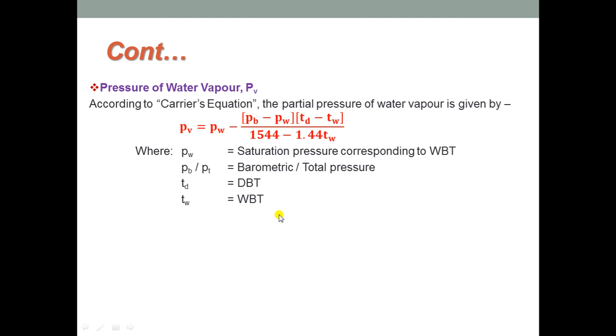Moving on to the next one, that is pressure of water vapor. According to Carrier's equation, the partial pressure of water vapor is given by the expression PV is equal to PW minus (PB minus PW) multiplied by (TD minus TW) over (1544 minus 1.44 TW), where PW is the saturation pressure corresponding to wet bulb temperature. PB or PT means barometric or total pressure. TD means dry bulb temperature. TW means wet bulb temperature.